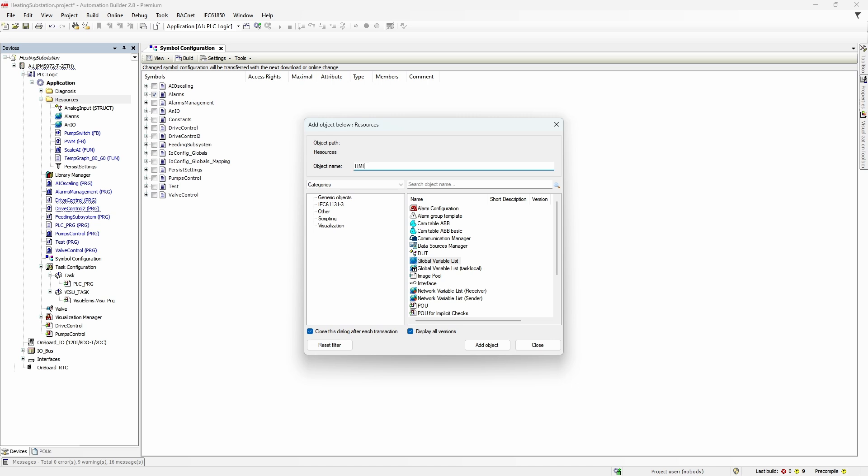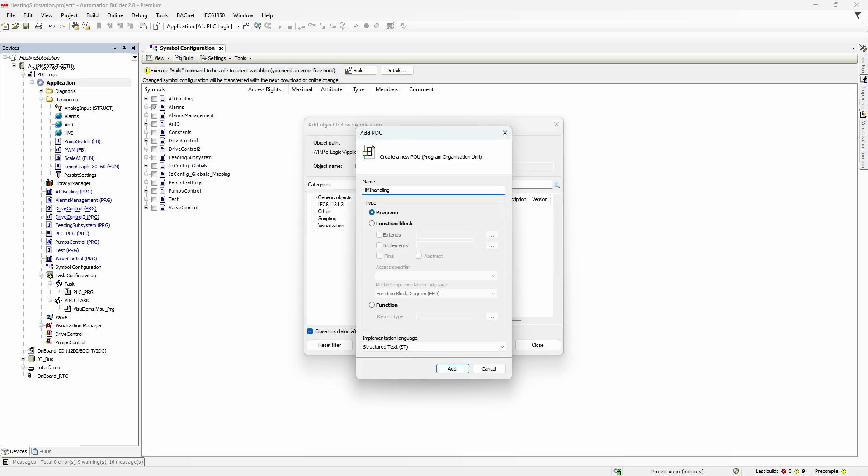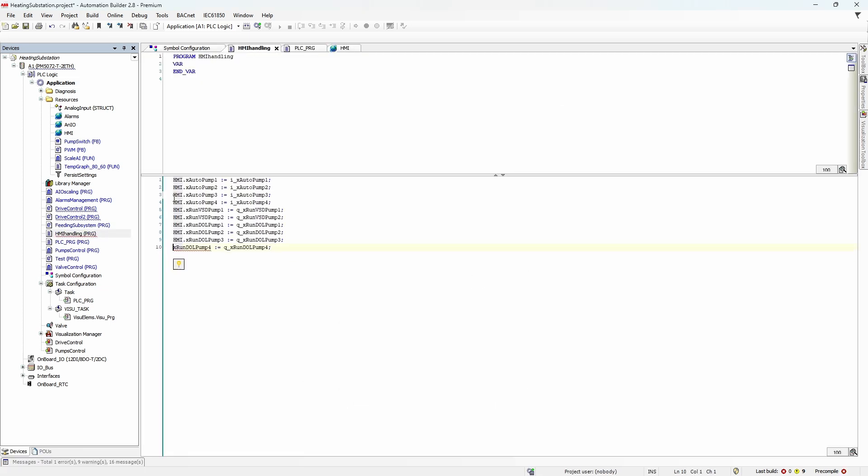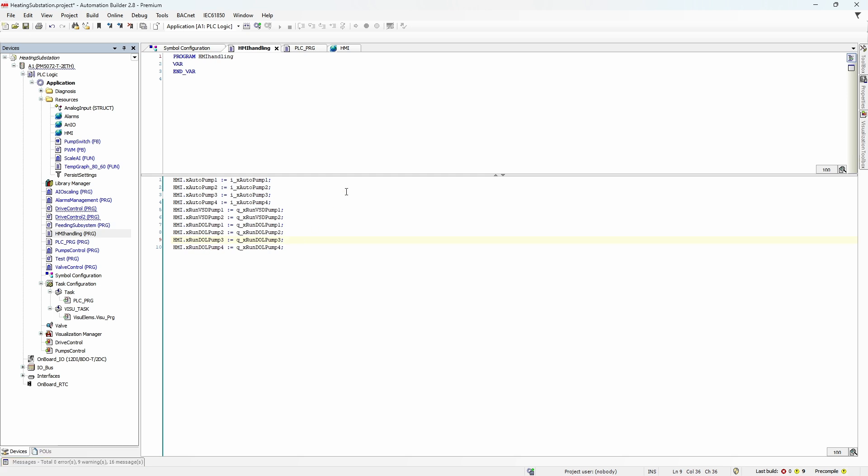In the majority of cases, you will not start developing the HMI straight after you finish the PLC part, but rather keep developing both parts in parallel. That means you will most probably need to pull more data from the PLC to the HMI over time. For example, I want to keep track of auto-manual switches and which pump is running. We have this data in the IOConfig global mapping, but giving direct access to physical inputs and outputs to the HMI is considered not good practice. Instead, I will create another variable list, name it HMI, create a new POU which will manage HMI-related data, and then copy the states of inputs and outputs to this newly created list.